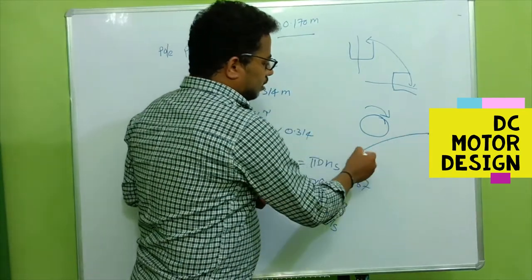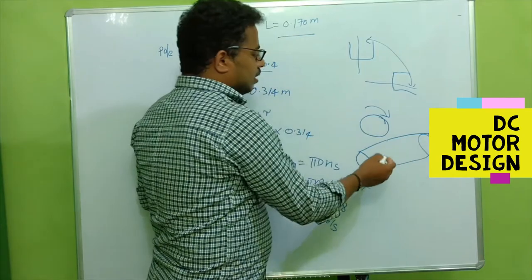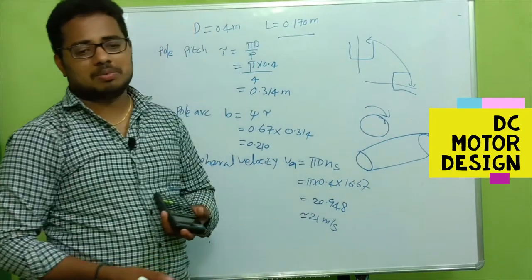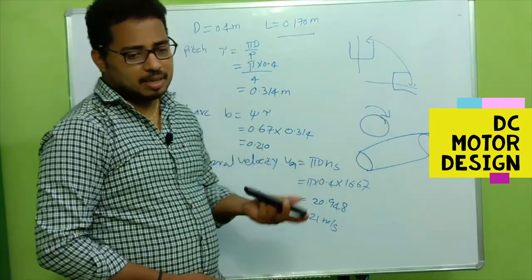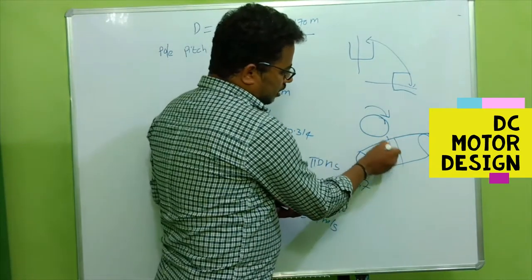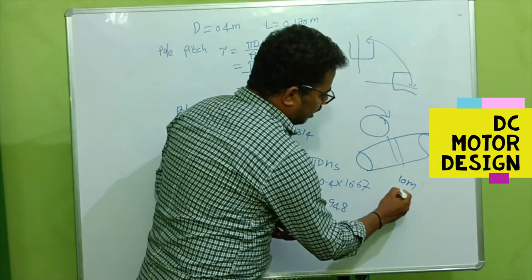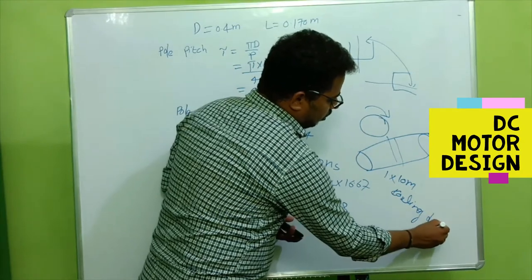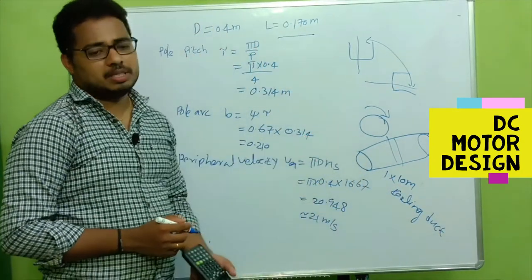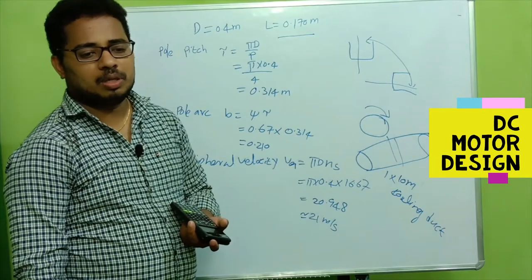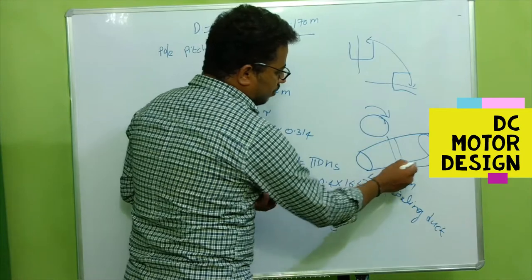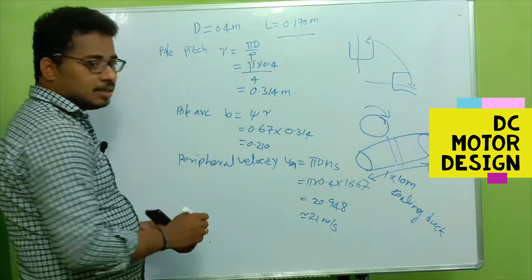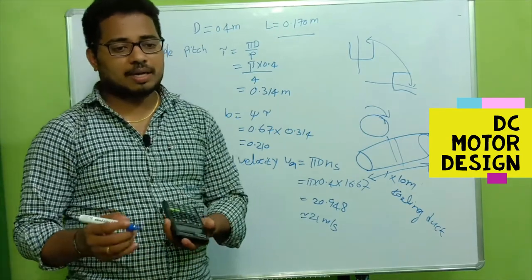We already calculated this length as 170 mm. This is a bigger length, so cooling becomes very difficult for the armature. For this much length, at least we should use one cooling duct - minimum one 10 mm cooling duct on this armature core. Then the cooling will be much better. From the entire length of 170 mm, we have to remove the cooling duct area to calculate net iron length.